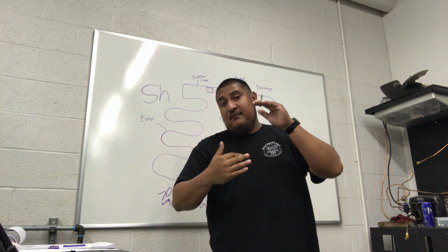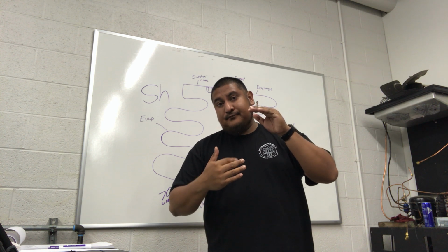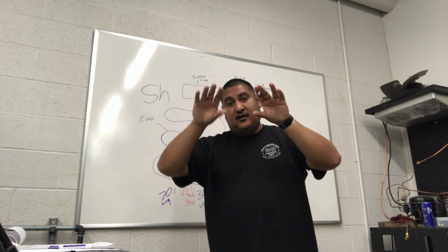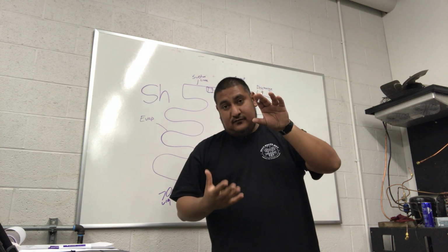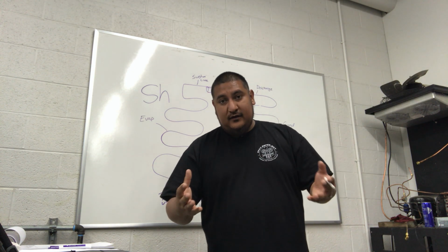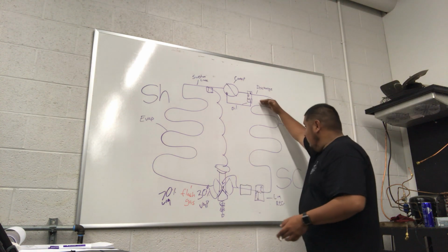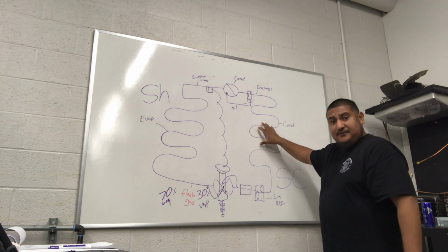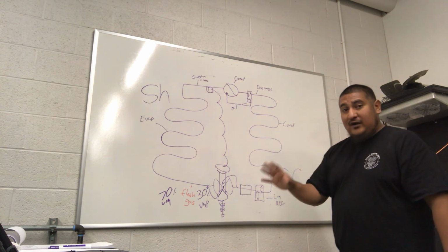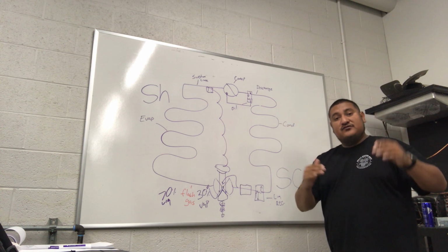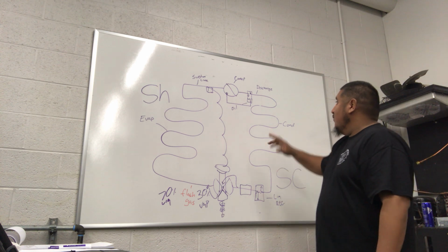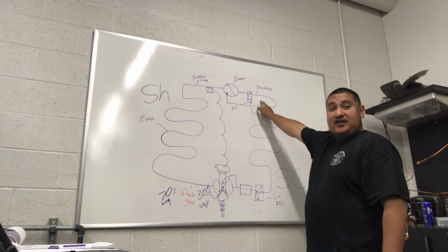If you're dropping temperature, right, we're actually going to go from a saturation where you got 50-50, right? We're dropping it, so we're making it cooler, right? So as we're making this refrigerant cooler, we're going to get liquid, right? So remember that condensing unit that's sitting over here, the condenser, right? That's what its job is, to give you liquid, right? So we want to have subcooling. We want to have some degree of subcooling. So the way we measure subcooling is we take our discharge pressure, or high side pressure, right?